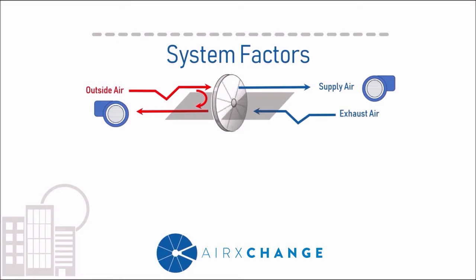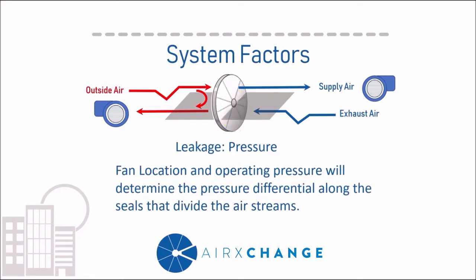What are the primary drivers that affect leakage? In comfort conditioning applications, leakage and carryover are the primary drivers determining EATR and OACF. Leakage is a function of pressure — and what determines pressure in a cabinet? Your fans do, more specifically the fan location and the operating pressure as it corresponds to the energy recovery component. Each component has seals on both the building side and the outdoor air side. The static pressure determines the pressure differential across those seals. The greater the differential, the greater the driving mechanism for leakage.